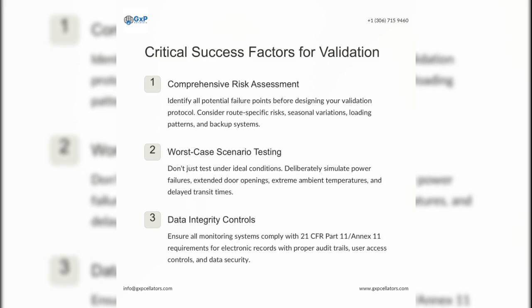Critical success factors for validation include comprehensive risk assessment, worst-case scenario testing, and data integrity controls. Identify all potential failure points before designing your validation protocol. Test under ideal and worst-case conditions, deliberately simulating power failures, extended door openings, ambient temperature changes, and delayed transit times. Ensure all monitoring systems comply with 21 CFR Part 11, Annex 11 requirements for electronic records with proper audit trails, user access controls, and data security.